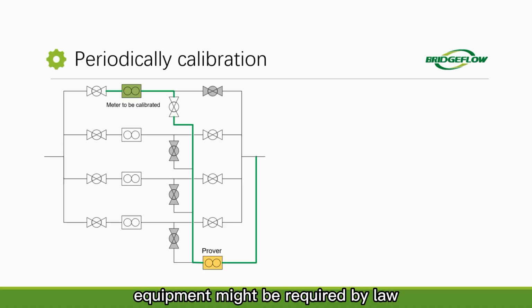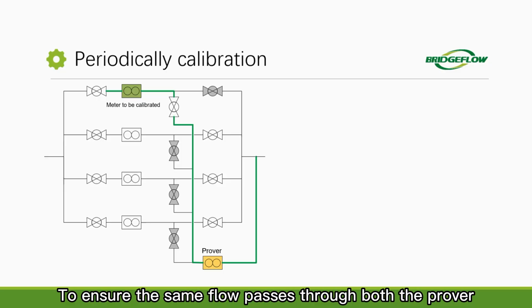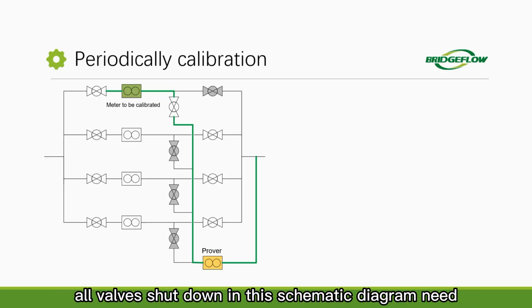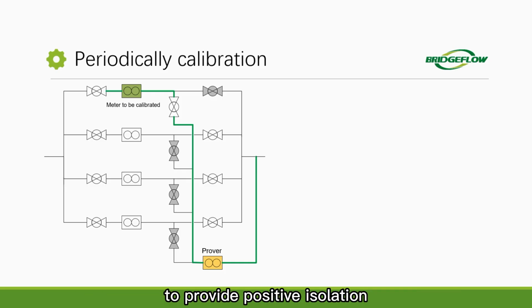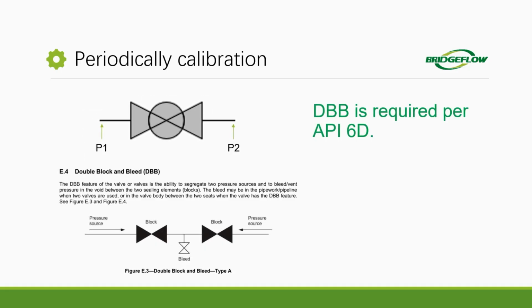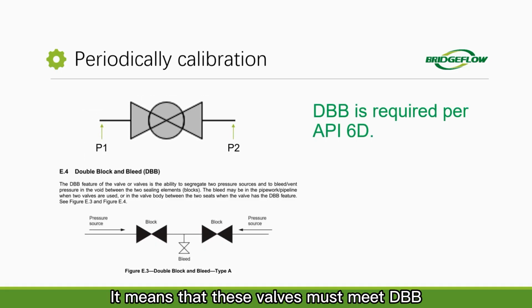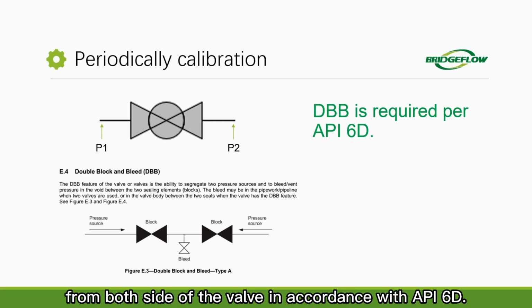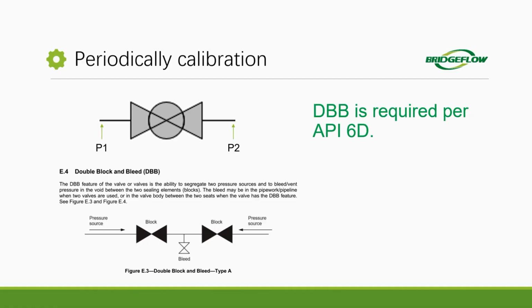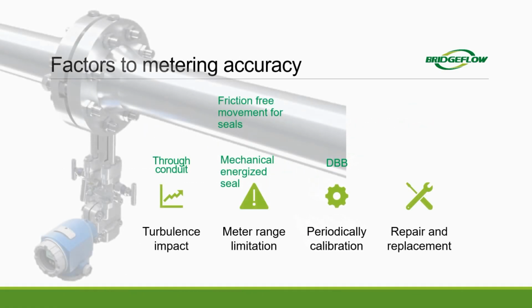Periodic calibration of metering equipment might be required by law in many cases. This is a typical online calibration layout. To ensure the same flow passes through both the prover and the meter to be calibrated, all valves shut down in this schematic diagram need to provide positive isolation with proven zero leakage. This is essential for ensuring the accuracy and reliability of the calibration process. It means that these valves must meet DBB to provide proven isolation under pressure from both sides of the valve in accordance with API 6D. Number 4. Valve feature required is DBB.